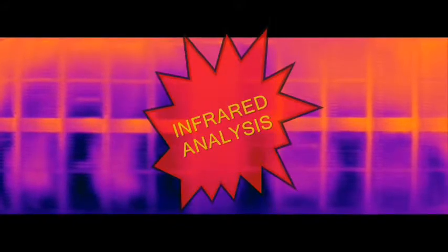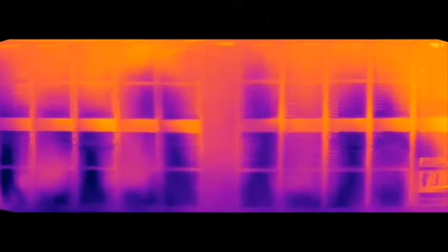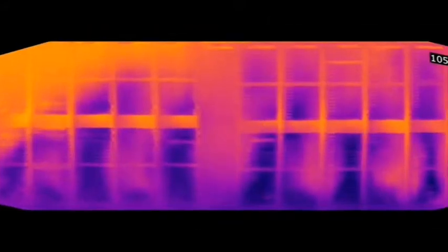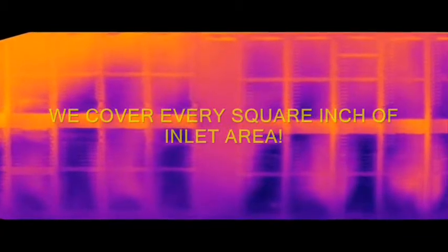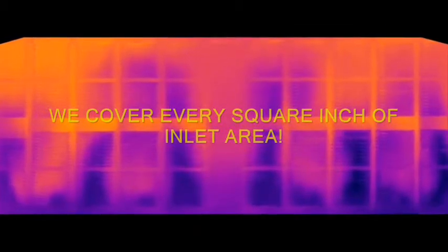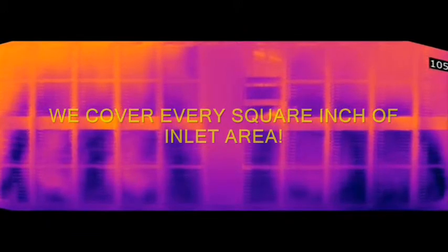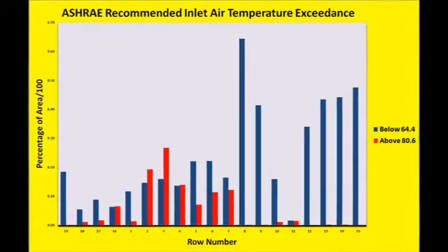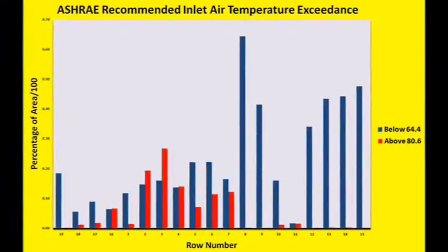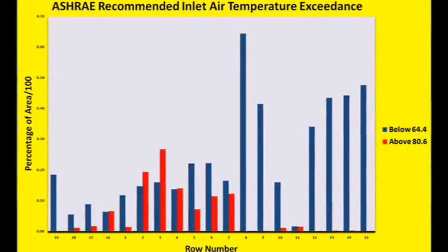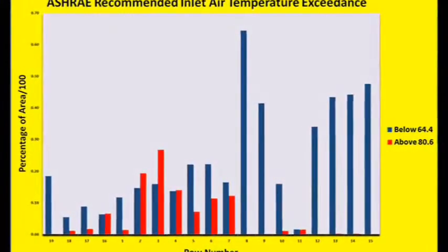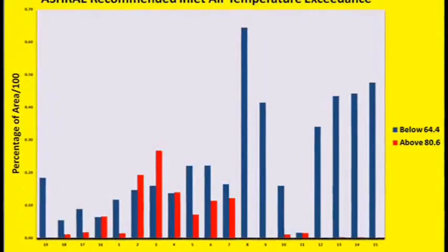We use high-resolution panoramic infrared images to supplement data from the DAM tool. We can determine precisely where airflow and cooling deficiencies exist. Further, we quantify the severity of such deficiencies. For example, this plot here shows percentages of average rack inlet temperatures that are above or below the ASHRAE standard recommended range for each row in the data center.